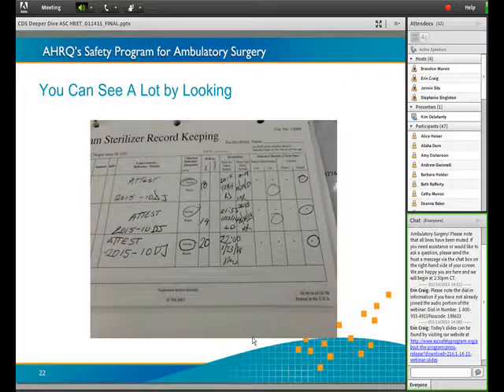Reports should be made to the Infection Control Committee, also your biomed teams. So if there is a machine that's not working properly and you've tried, you've done a redo of your QC, then that needs to be taken offline until biomed can come and make sure it's working correctly, or maybe it needs to be taken offline so they can fix it. And note that the control on the log sheet is always positive.